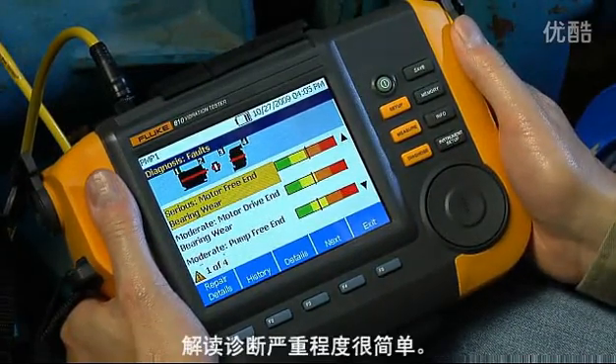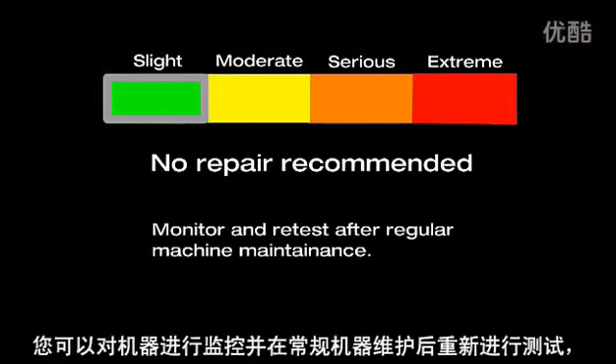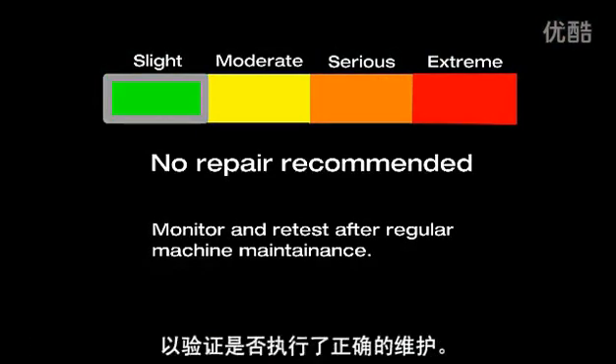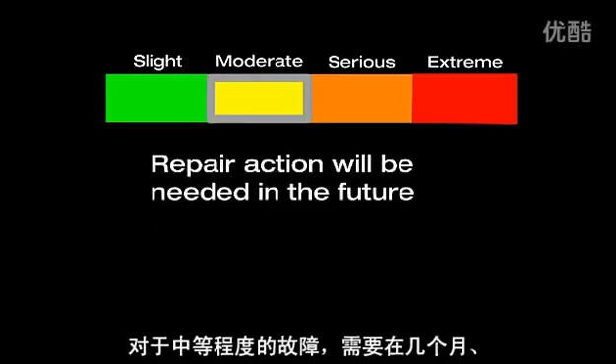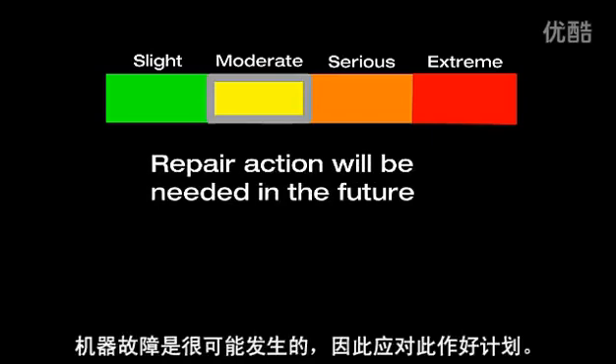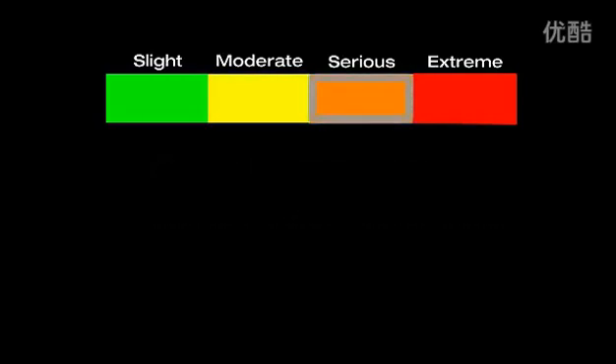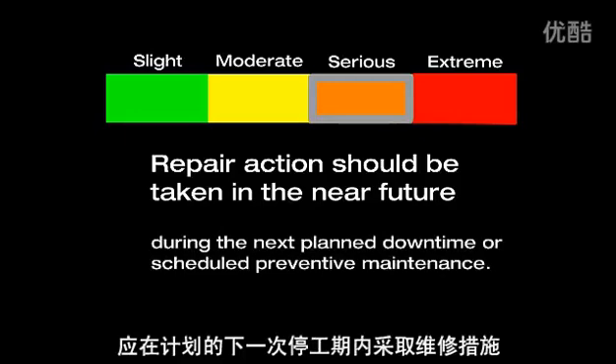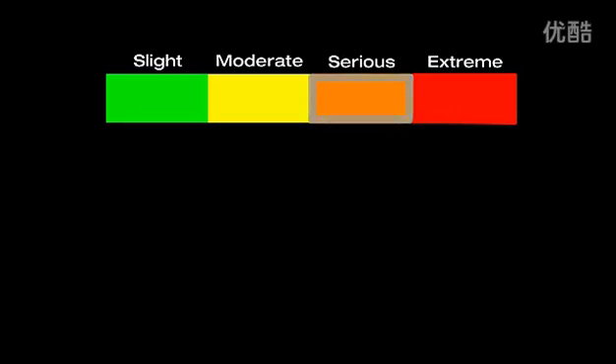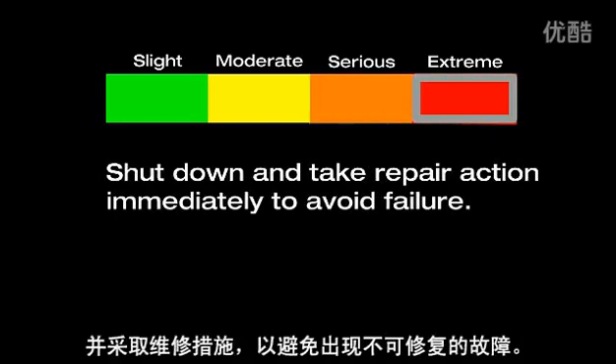Interpreting the diagnostic severity scale is simple. For slight faults, no repair action is recommended — monitor the machine and retest after regular maintenance to verify it was performed correctly. For moderate faults, repair action will be needed within months, even up to a year; a machine failure is possible, so plan for it and review spare parts availability. For serious faults, repair action should be taken during the next planned downtime or scheduled preventive maintenance. For extreme faults, it is recommended to shut down and take repair action immediately to avoid failure.